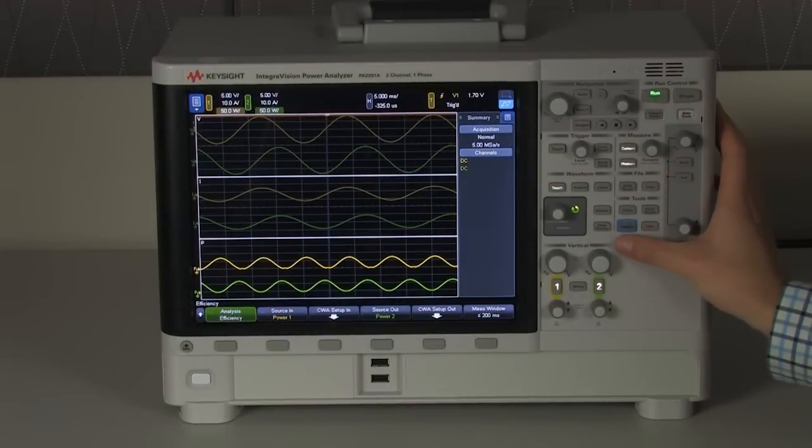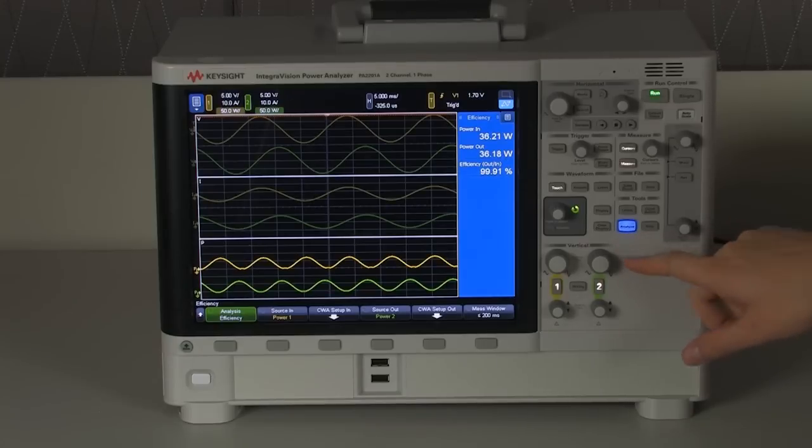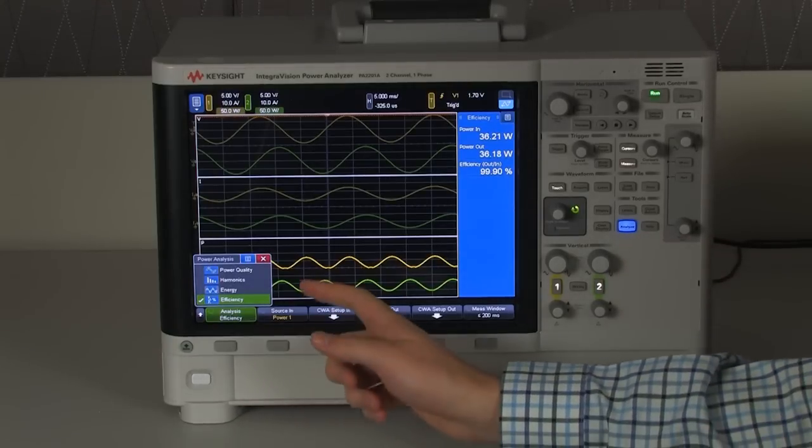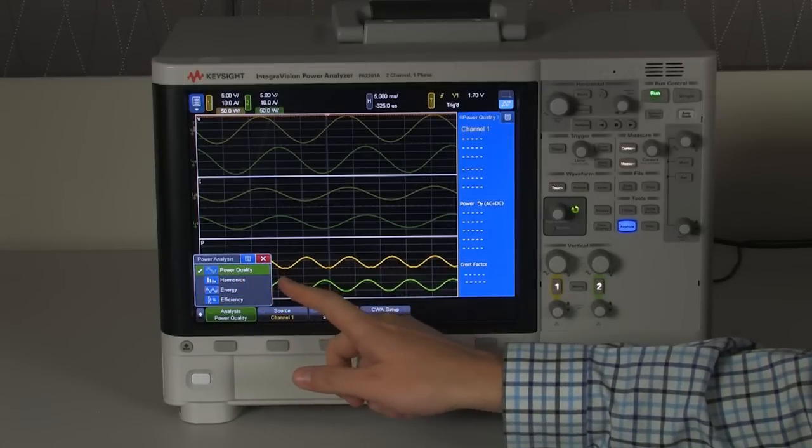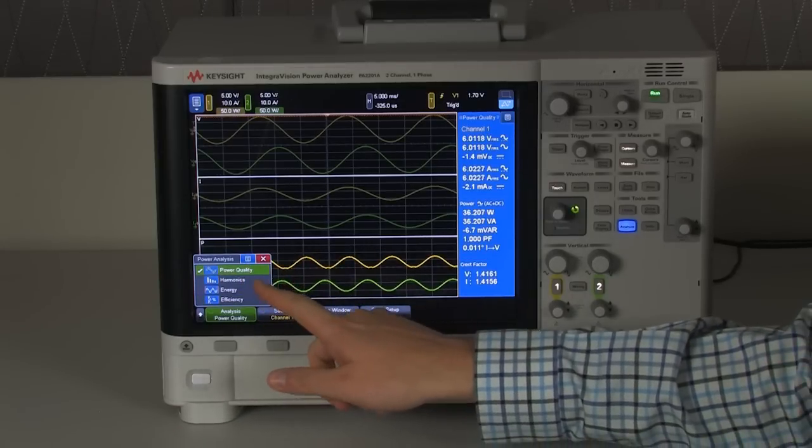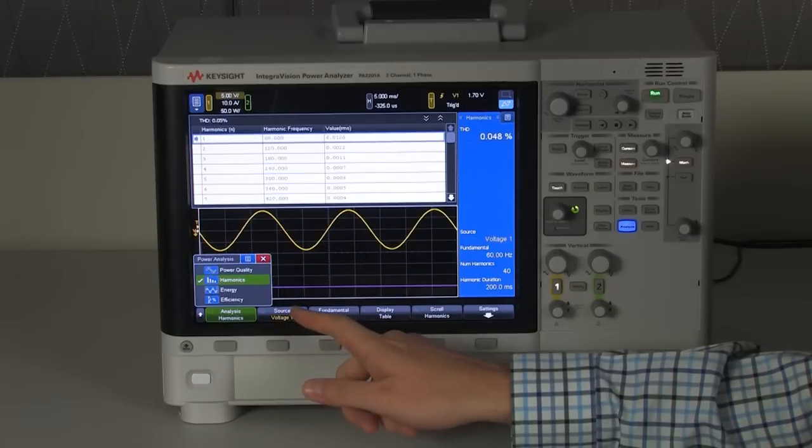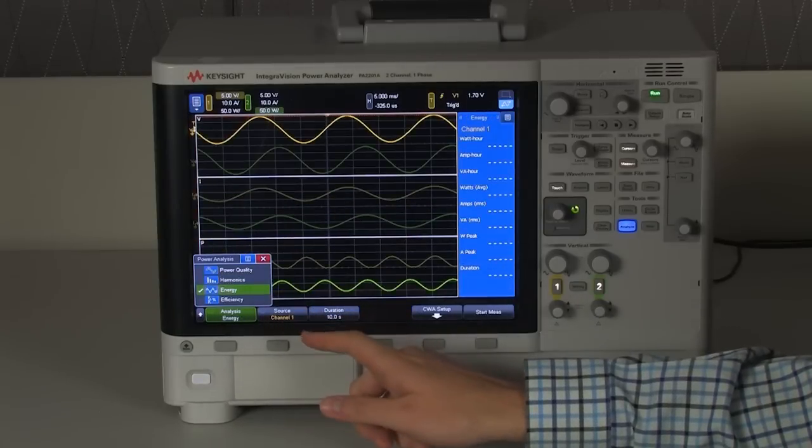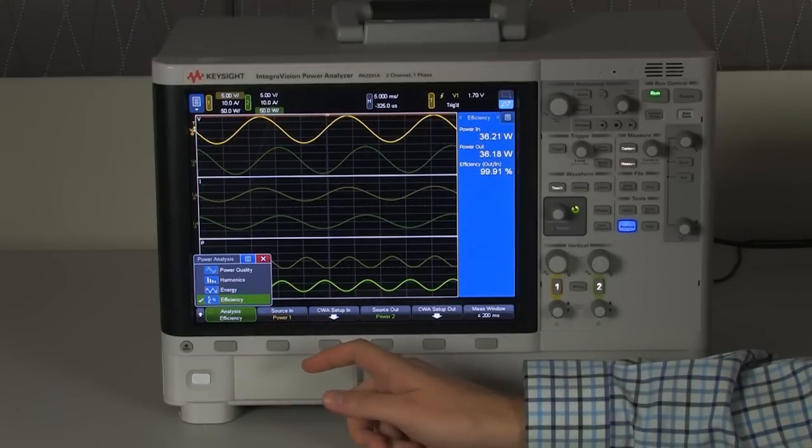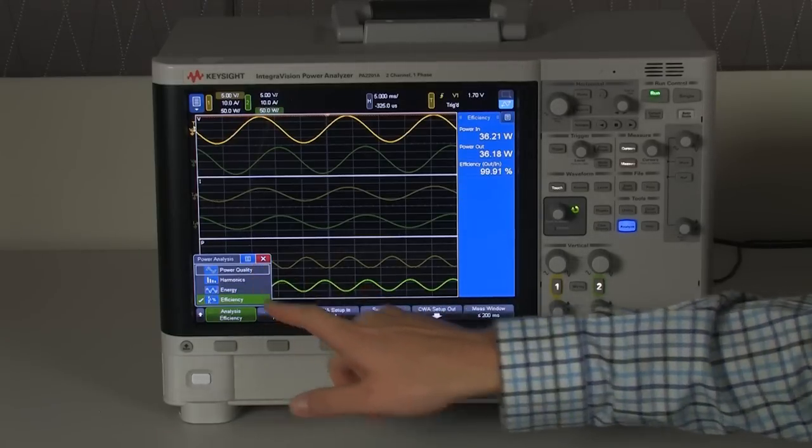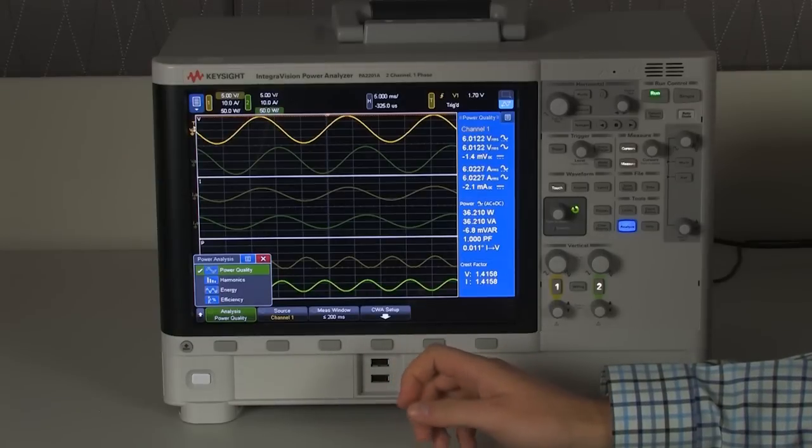So, now we're going to talk about the continuous whole cycle analysis mode of the IntegraVision Power Analyzer. So, if I go into the CWA mode, we have four different major categories of stuff we can measure. We can get basic power quality measurements on our waveforms. We can measure harmonics of our waveforms. We can measure energy over time of our waveforms. And we can also measure the real-time efficiency.